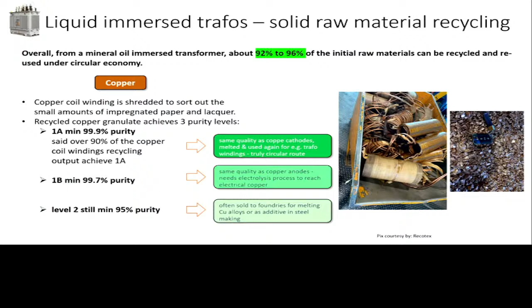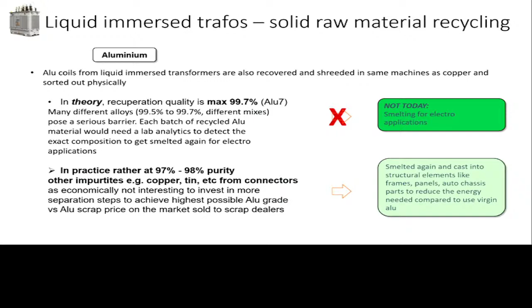One limitation, where I'm also part of it, is for the conductor to get recirculated in cast coils. That's why everyone today prefers, in dry type transformers, the low voltage winding to be a foil, which is VPI and can be retrieved, whereas for high voltage winding people use aluminum, and that retrieval is a costly affair. Except for that limitation, the technology has fantastic benefits, but it's always a negative compared to any liquid-filled transformer.